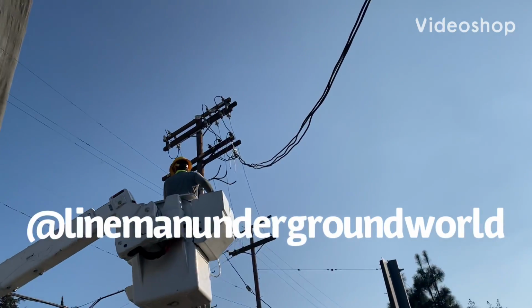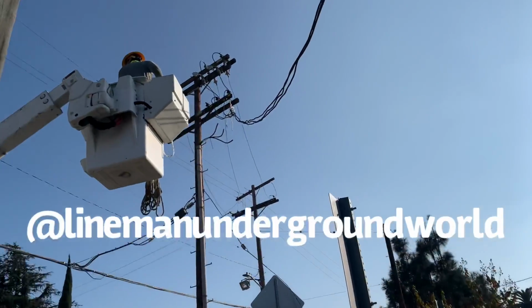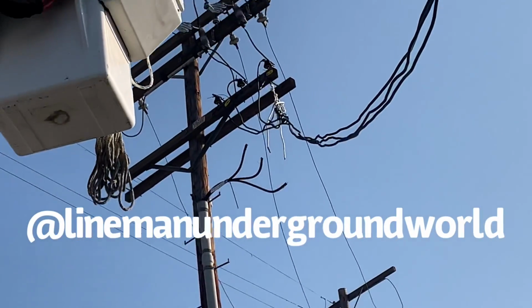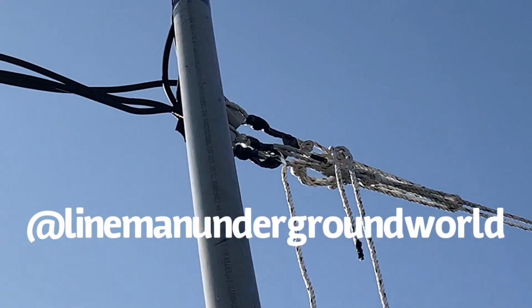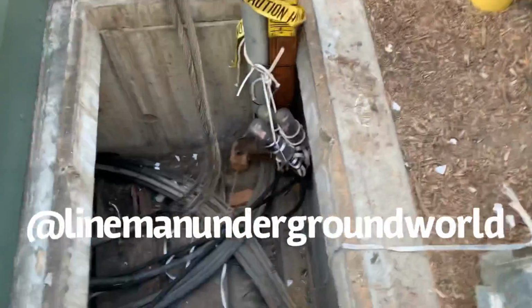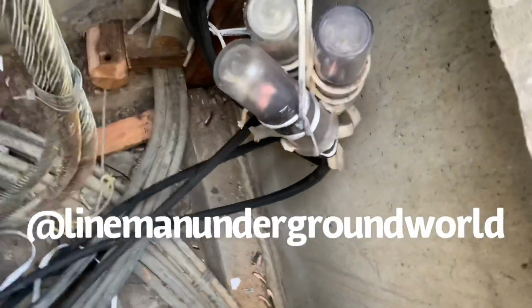Job. Primaries look like they burned up from the pole over there to the riser. And let me see if I can blow her up. As you can see right there, we got the temp jumpers coming this way up here, and she's coming down.